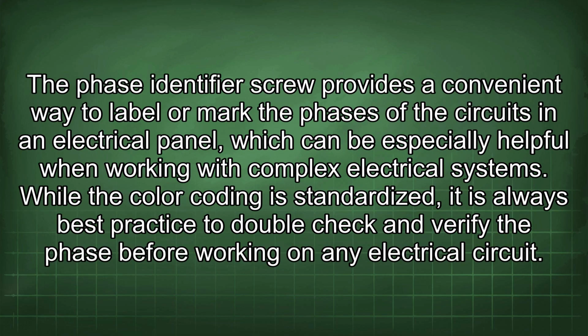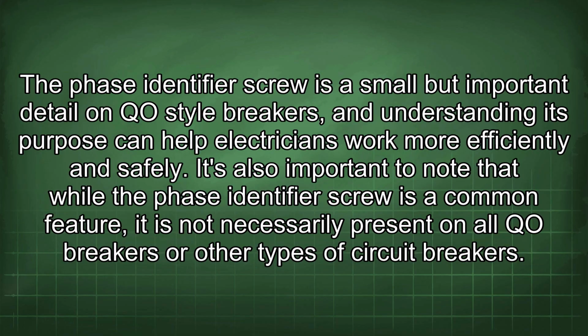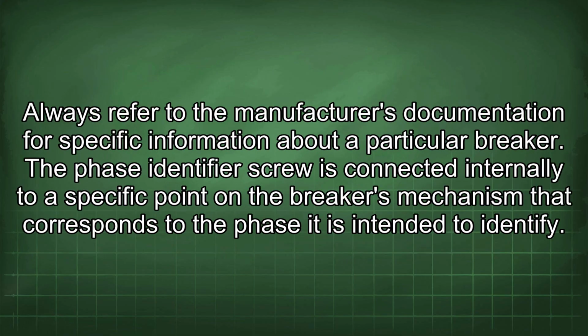The phase identifier screw provides a convenient way to label or mark the phases of the circuits in an electrical panel, which can be especially helpful when working with complex electrical systems. While the color coding is standardized, it is always best practice to double-check and verify the phase before working on any electrical circuit. The phase identifier screw is a small but important detail on QO-style breakers, and understanding its purpose can help electricians work more efficiently and safely. It's also important to note that while the phase identifier screw is a common feature, it is not necessarily present on all QO breakers or other types of circuit breakers. Always refer to the manufacturer's documentation for specific information about a particular breaker.